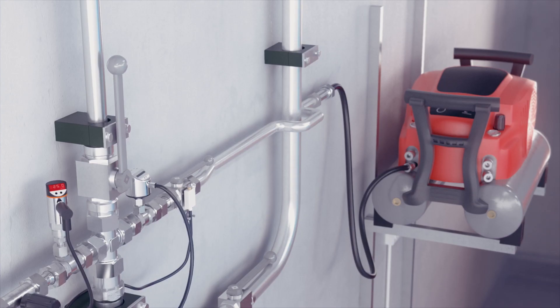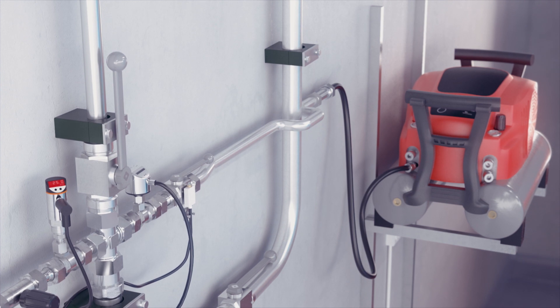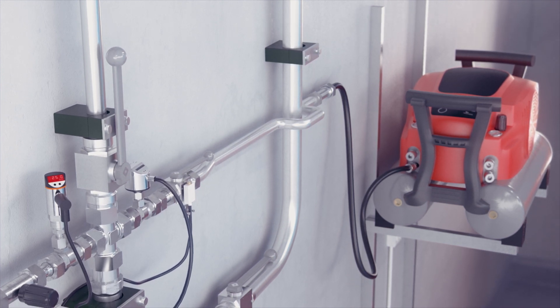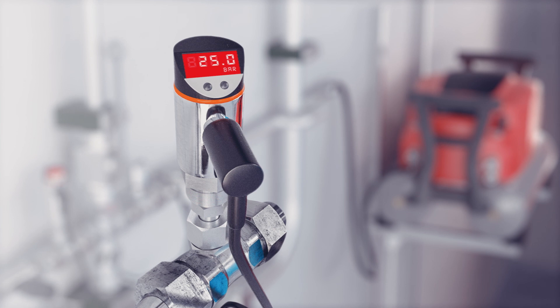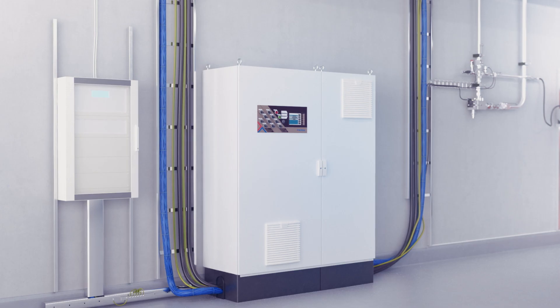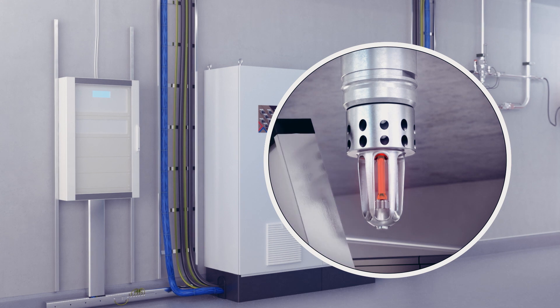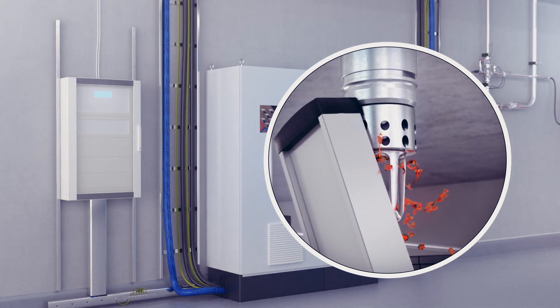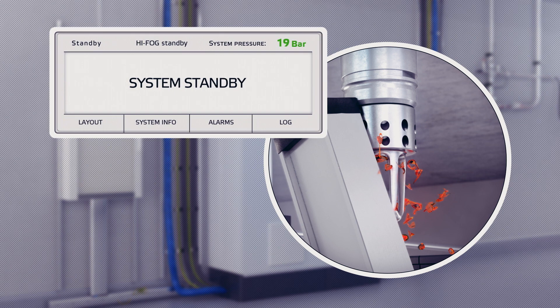In a normal situation, the pipes in the data hall are pressurized with air. This helps in monitoring the whole system and makes sure the sprinklers are unbroken when the system is in standby mode. If a sprinkler bulb breaks accidentally, only pressurized air escapes the sprinkler and the system generates an alert signal.